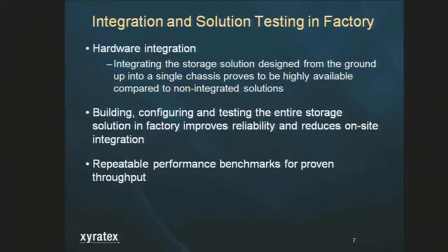And then lastly, integration is also key. When I talk about integration, it's the level of testing and manufacturing that goes into integrating the disk drives into the storage controllers, into a rack, configuring the software stack, and purpose-building the solution for file system performance and availability. It includes a lot of soak testing, vibrational testing, and running through various cases of failures to ensure all this manufacturing, integration and testing is done before it hits the customer site. At the end of the day, we can find a lot of the issues in manufacturing, rather than the customer seeing failures when the system hits the site. A lot of the integration methodology in manufacturing finds many of the problems before it hits the customer site and avoids on-site integration, which also increases the overall reliability and availability of the system.